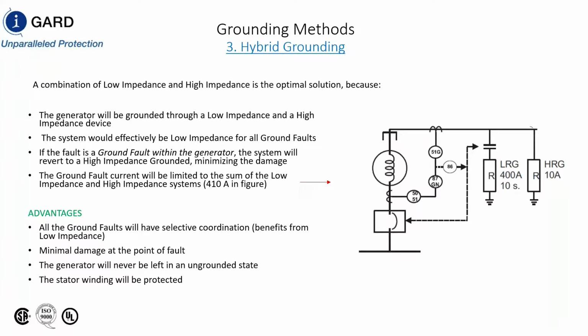And you don't have this. So you want to open up this breaker and remove the generator breaker, or the neutral grounding return path for the generator when the differential picks up.